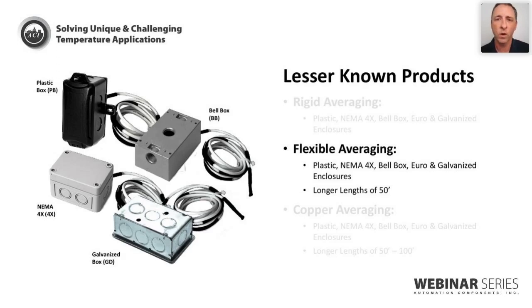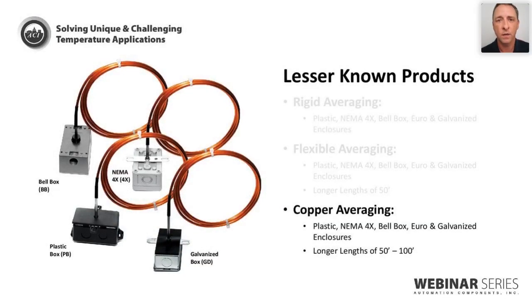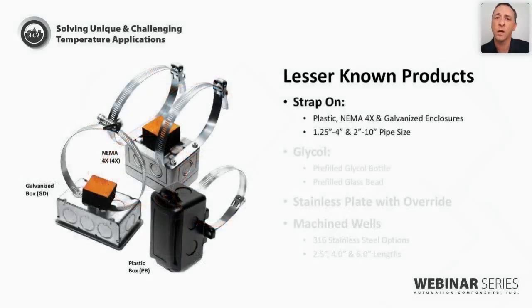The highlight I wanted to point out today is that we do have these available in lengths of up to 50 feet for thermistors. As air handlers get bigger and bigger, we're seeing requirements for longer and longer averaging sensors. So with a flexible averaging sensor, we can build those of up to 50 feet. And for a copper averaging, we can build those up to 100 feet in length. So for thermistors, 50 feet is the longest we can do. For RTDs and 4-to-20 or analog transmitters, we can build those in lengths of up to 100 feet. And we can do custom lengths as well.